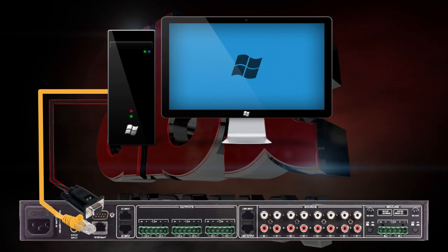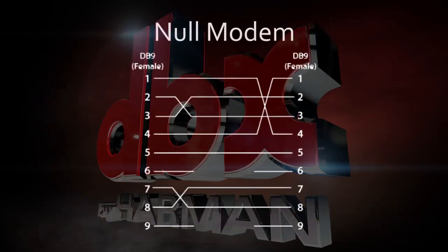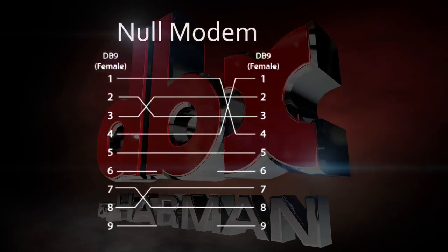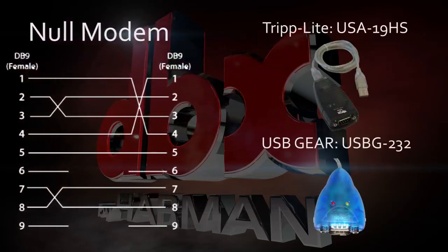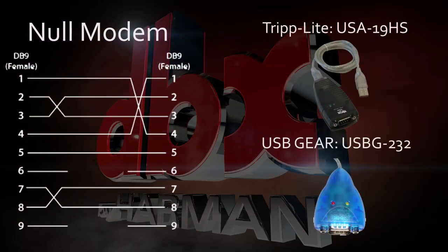Note that you cannot use a straight-through RS-232 cable. Null modem cables have pins that cross as shown here. If you're using a null modem to USB adapter, make sure that you're using one of these tested cables and that you have installed the driver for that specific adapter.